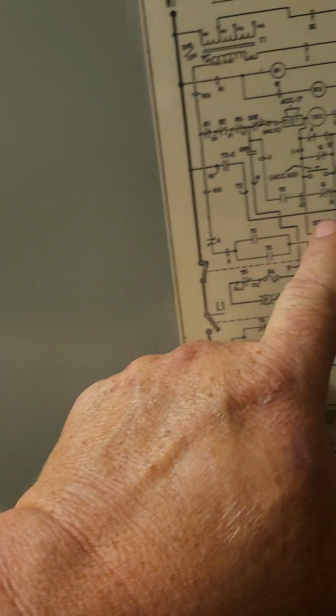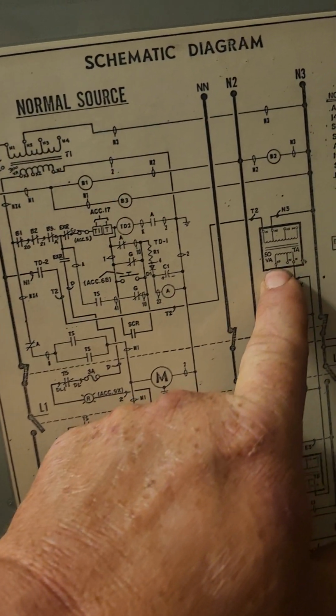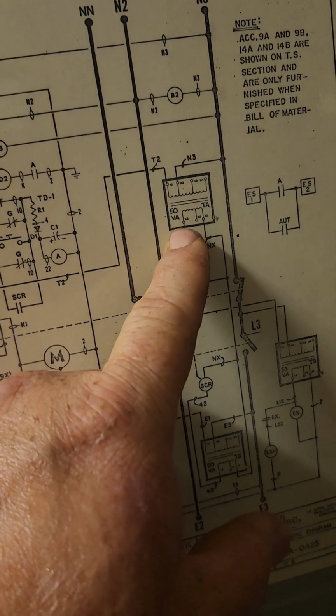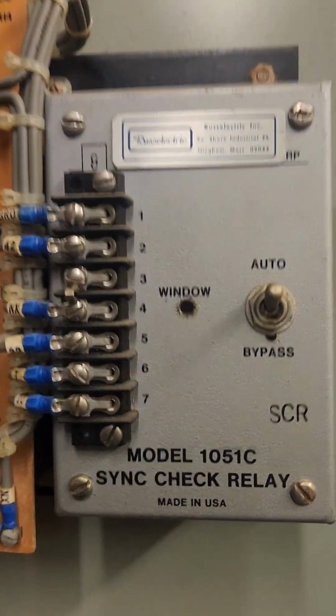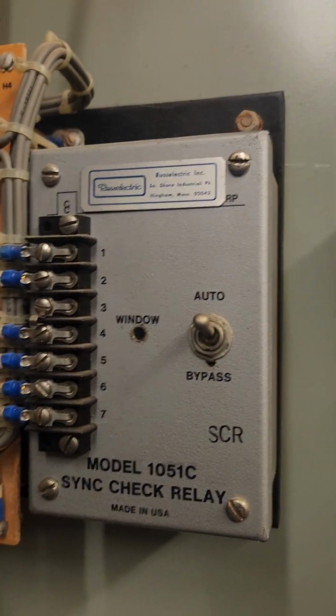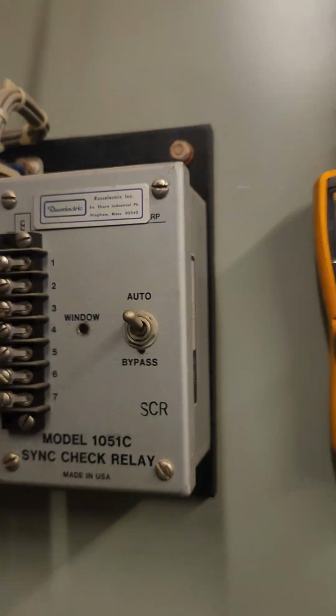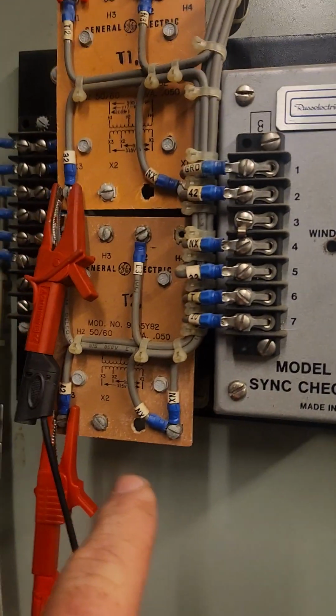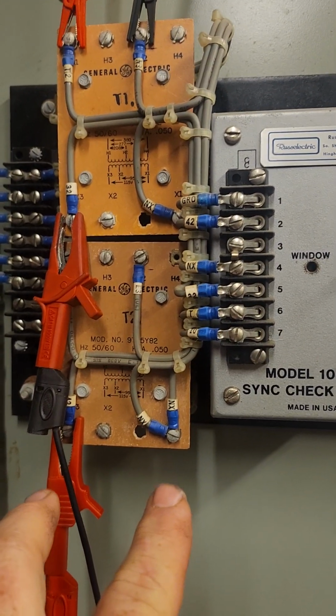That's getting satisfied, and what it breaks power to the normal transformer, that steps down and goes to the sync check relay, and basically it's just in-phase transfer. For emergency power comes straight through, there's nothing that's breaking the emergency power.